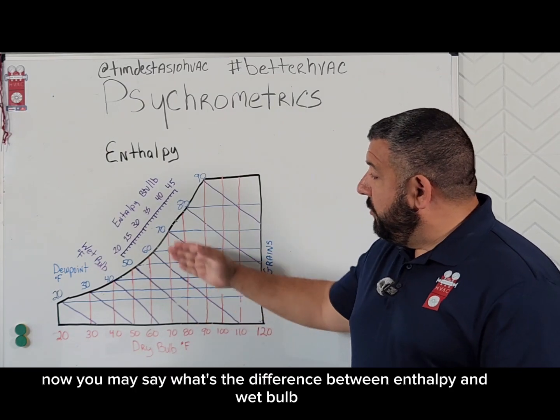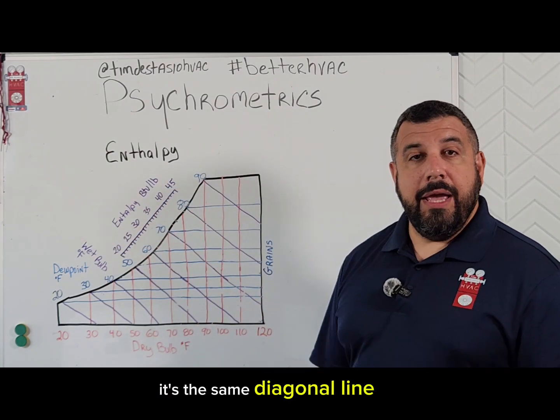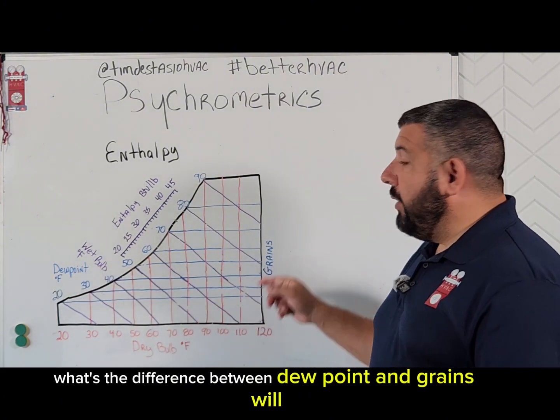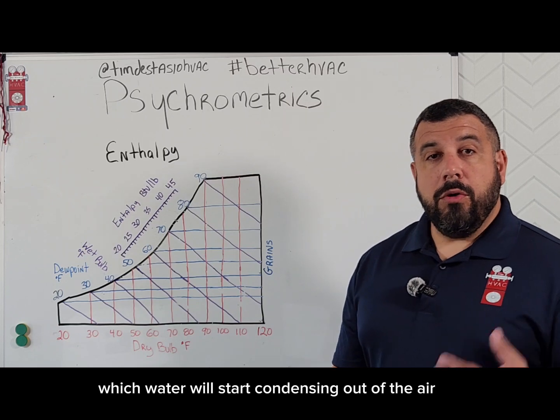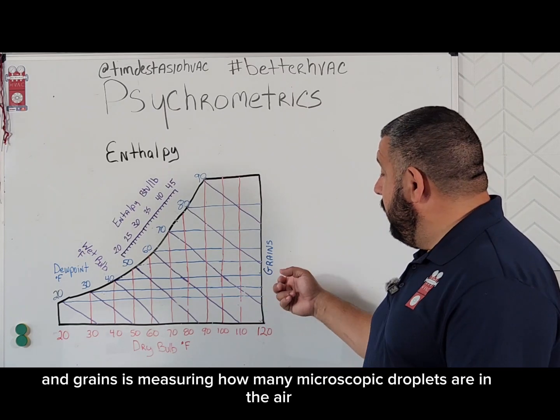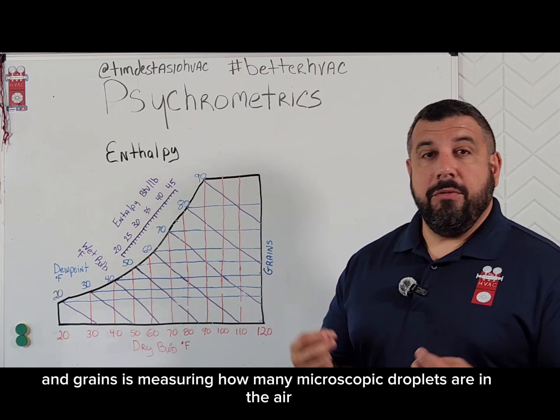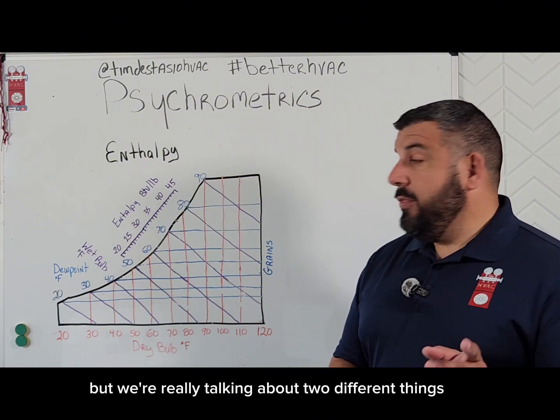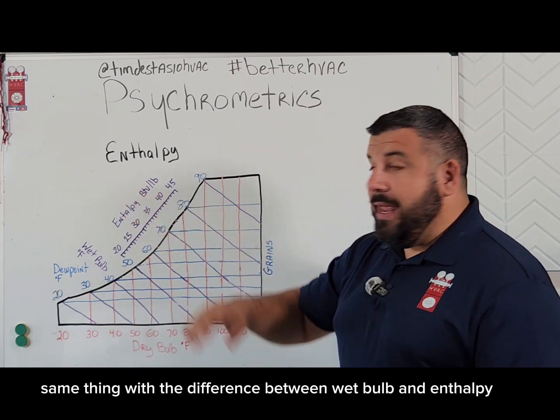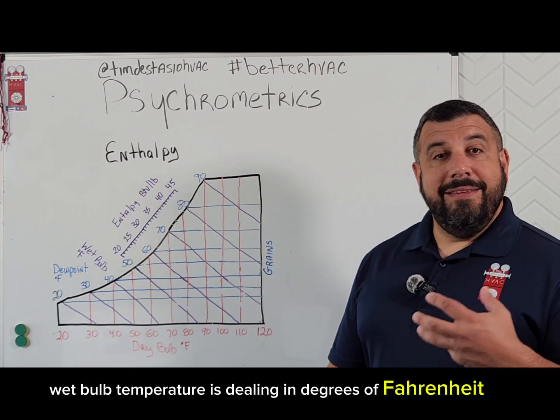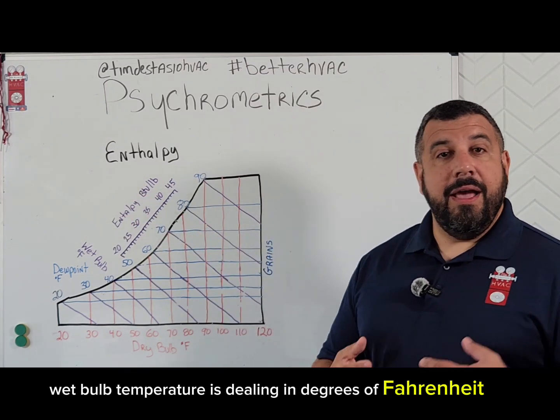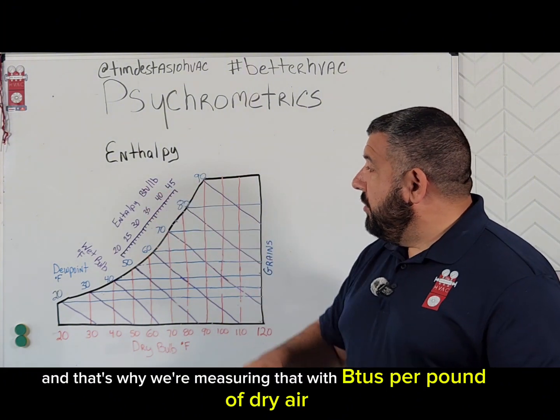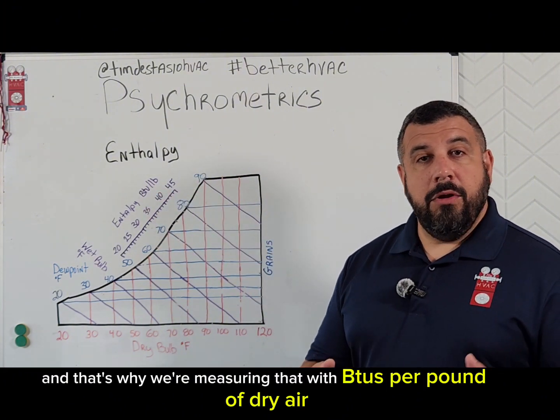Now you may say, what's the difference between enthalpy and wet bulb? It's the same diagonal line. Well, it's very similar to asking what's the difference between dew point and grains. Dew point is measuring the temperature at which water will start condensing out of the air, and grains is measuring how many microscopic droplets are in the air. So we're using the same line, but we're really talking about two different things. Same thing with wet bulb and enthalpy — wet bulb temperature is dealing in degrees Fahrenheit, it's a temperature, but enthalpy is measuring energy. And that's why we're measuring that with BTUs per pound of dry air.